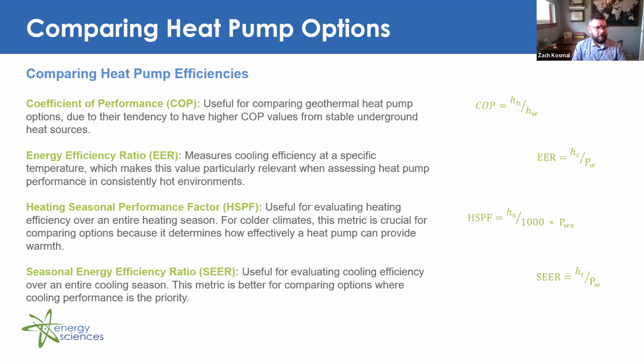Heating seasonal performance factor. So just a reminder, that is your heat produced during the season divided by your electrical power consumed during that season. So this is useful for evaluating heating efficiency over an entire heating season, right? So for colder climates, this metric is crucial for comparing options because it's determining how effectively a heat pump can provide warmth, right? So that's going to be our most common metric used in this part of the US.